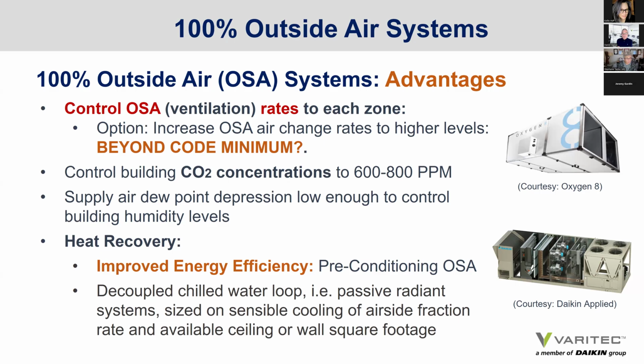So a 100% outside air system allows you to inject that outside air directly to each zone. It can also help control the concentration of CO2 levels that ASHRAE is evaluating today, in fact. There are papers out there suggesting that CO2 levels should be limited to not exceed 1,000 parts per million, and there are even some reports in the ASHRAE Journal that maybe the target should be 600 to 800 parts per million. The only way to control CO2 today, without some pretty compelling new technology that's just beginning to get into the industry, is to provide more outside air to your building.